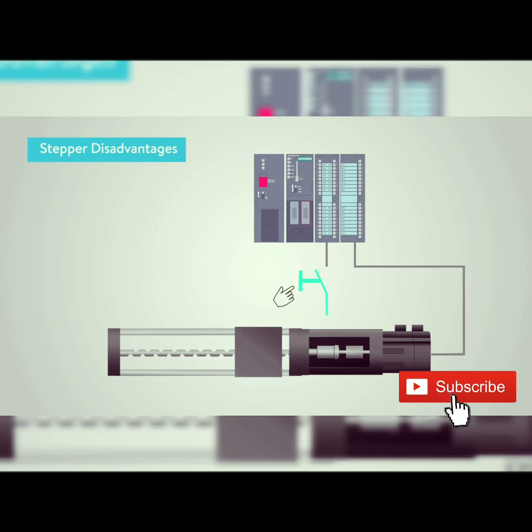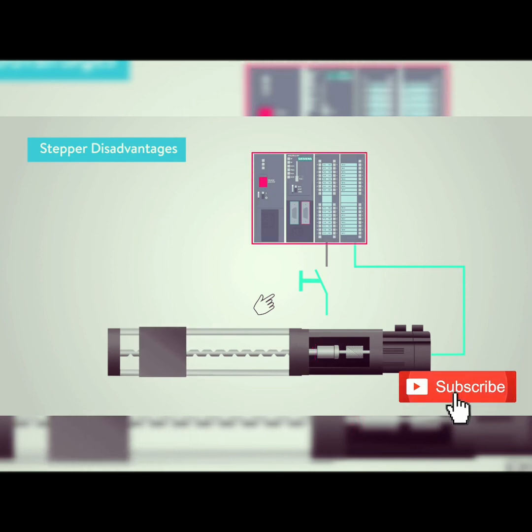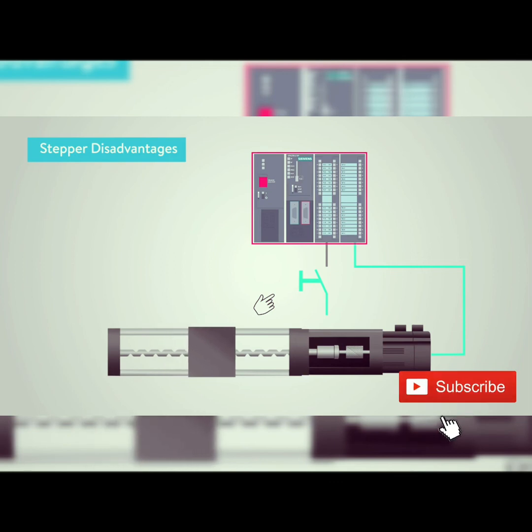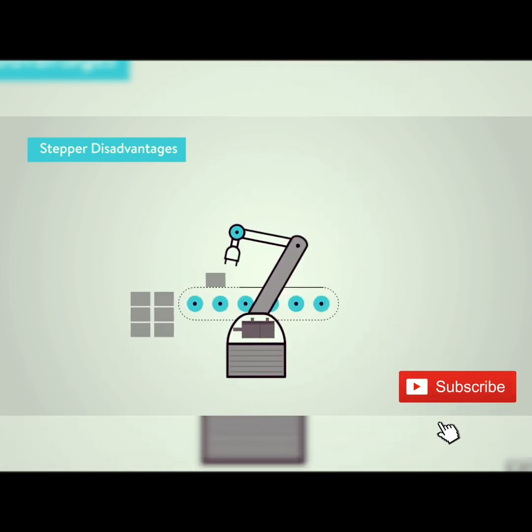And while speaking of open loop systems, a drawback of open loop control using steppers is that if the machine load is too high or the motor attempts to move too quickly, then positional steps may be skipped. The controller has no means of detecting this, and so the machine continues to run slightly out of adjustment until the position is reset. For this reason, more complex robots and machine tools will utilize servo motors that incorporate encoders and closed loop controllers.